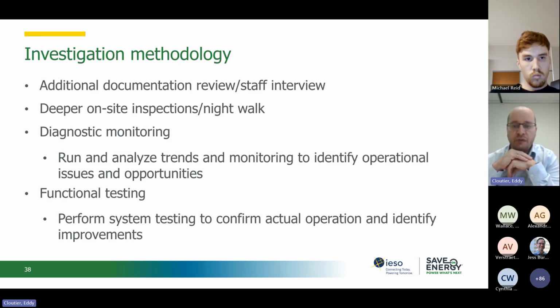This activity will often make it possible, within a few hours, to detect ventilation systems, pumps, exhaust fans, or lighting systems that remain in operation for no reason and often cause unnecessary energy consumption. It's a very simple activity to carry out, but it often pays off in existing building commissioning.